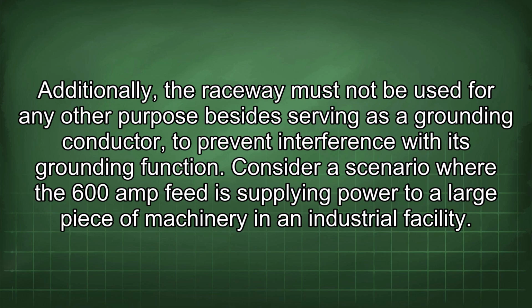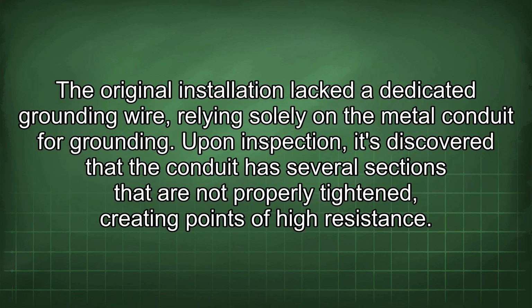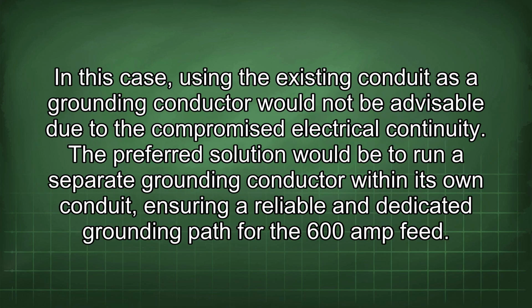Additionally, the raceway must not be used for any other purpose besides serving as a grounding conductor to prevent interference with its grounding function. Consider a scenario where the 600 amp feed is supplying power to a large piece of machinery in an industrial facility. The original installation lacked a dedicated grounding wire, relying solely on the metal conduit for grounding. Upon inspection, it's discovered that the conduit has several sections that are not properly tightened, creating points of high resistance. In this case, using the existing conduit as a grounding conductor would not be advisable due to the compromised electrical continuity. The preferred solution would be to run a separate grounding conductor within its own conduit, ensuring a reliable and dedicated grounding path for the 600 amp feed.